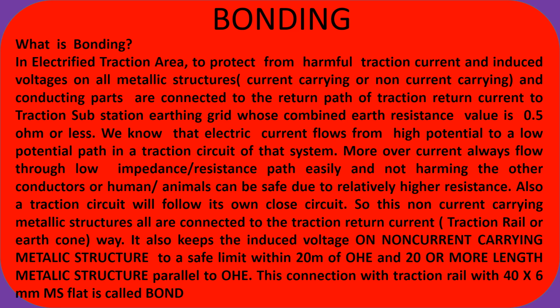So these non-current carrying metallic structures are all connected to the traction return current, traction rail, or earth cone. It also keeps the induced voltage on non-current carrying metallic structures to a safe limit within 20 meters of OHE, since across the overhead conductor, up to 20 meters is the harmful effect of induced voltage.